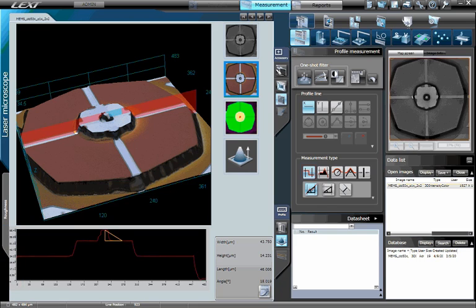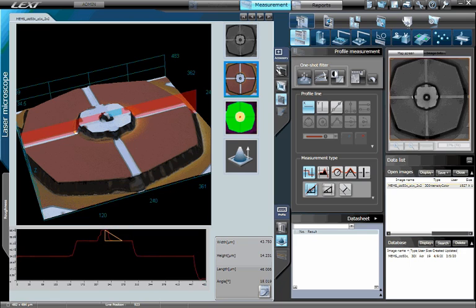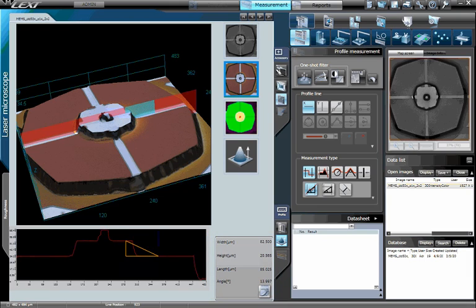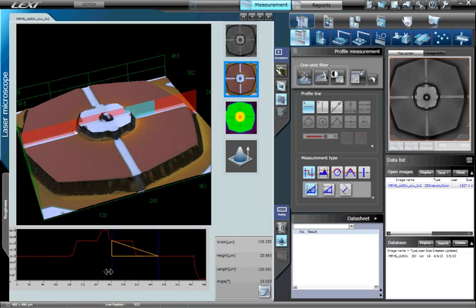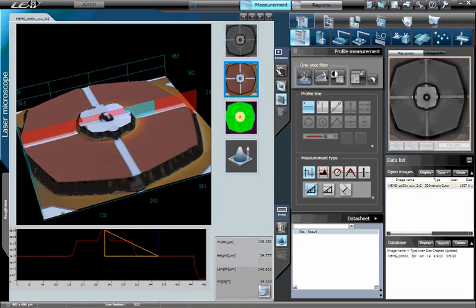By selecting the length measurement type, we can measure length, width, height, and angles across two user-definable points on the graph. The yellow triangle on the graph directly corresponds with the measurement parameters displayed on the right. Click on the left and right blue vertical lines and position them at the features of interest which you wish to measure across.